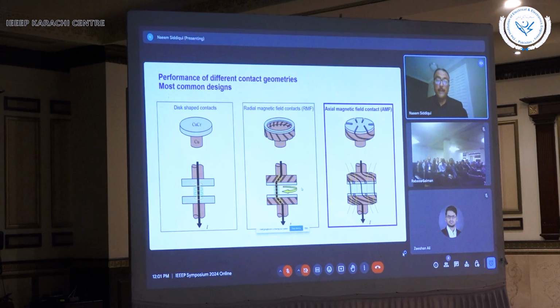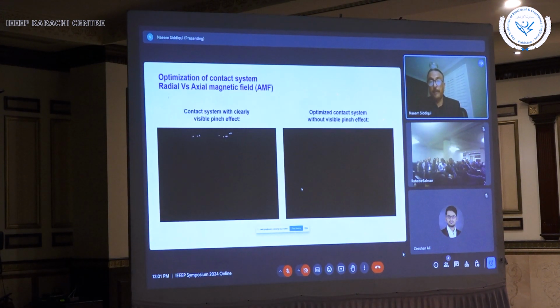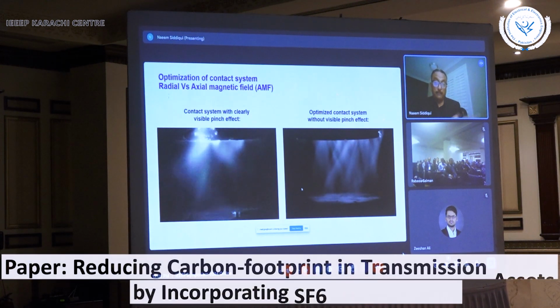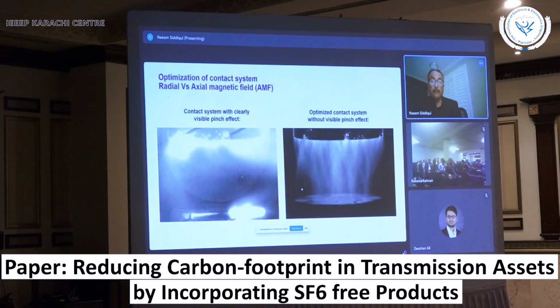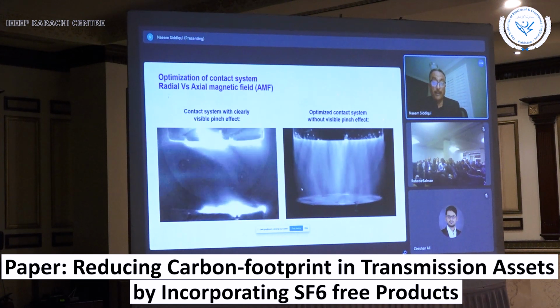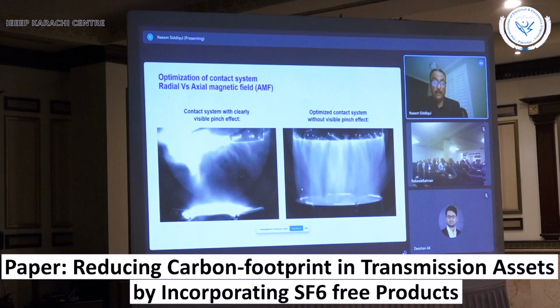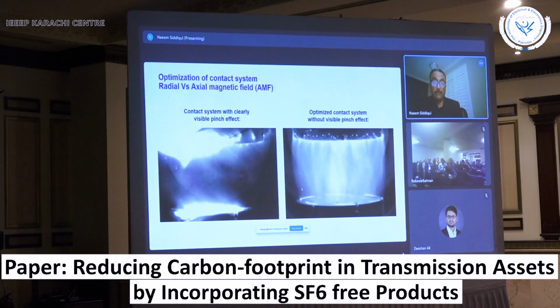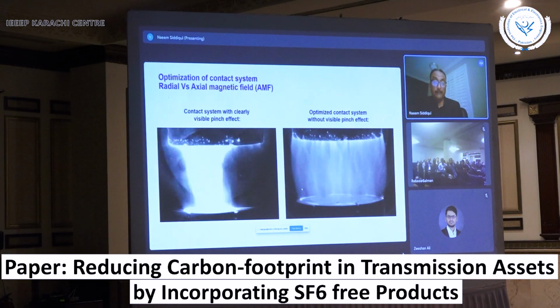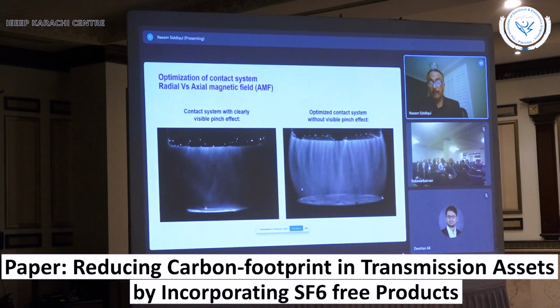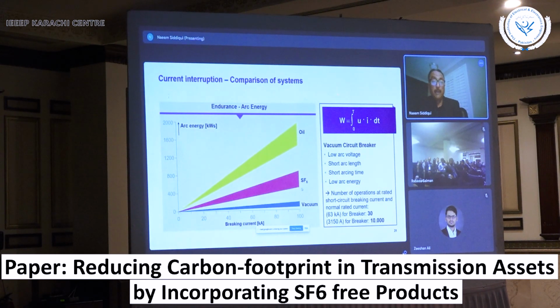This is inside of the contact system in the vacuum tube. You can see a special contact system. On the right side, this is the specialized contact Siemens designed for vacuum bottles for high voltage circuit breaker and GIS system, whereas the left side is the pinch effect, which is going on right now.